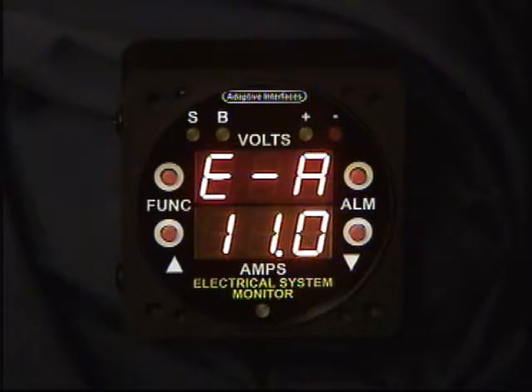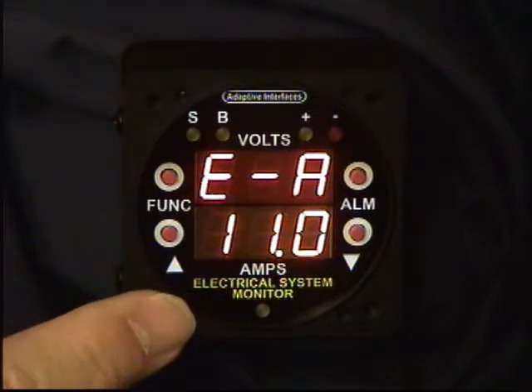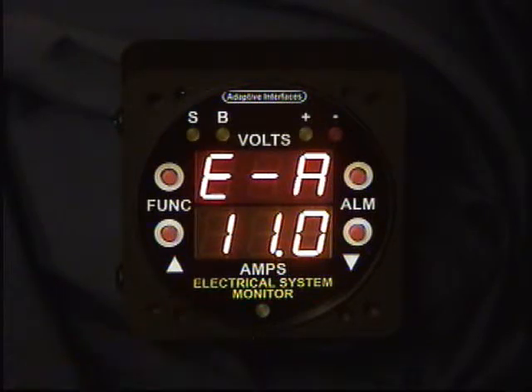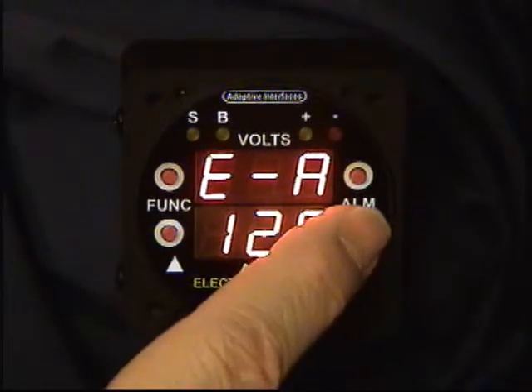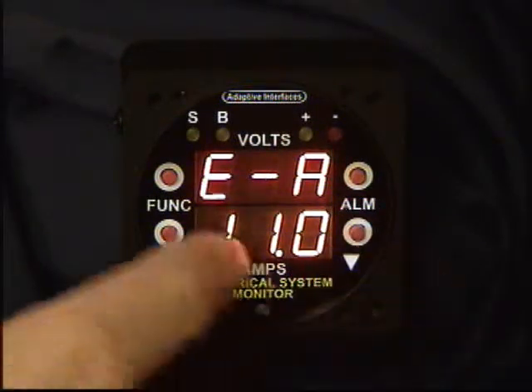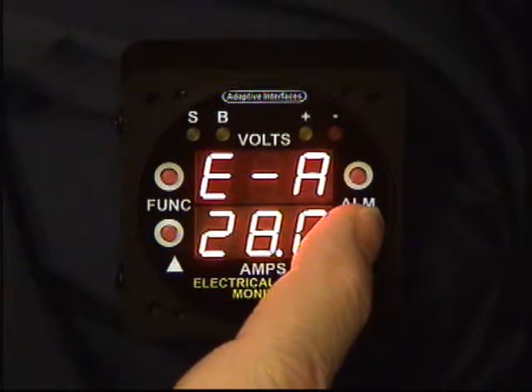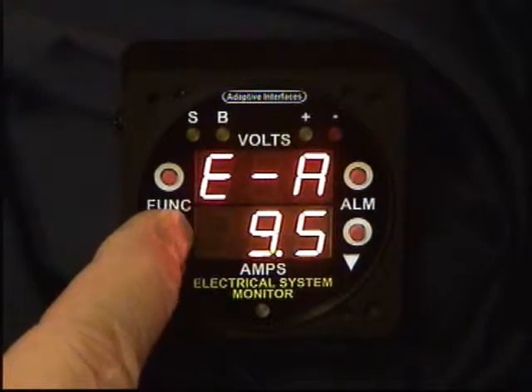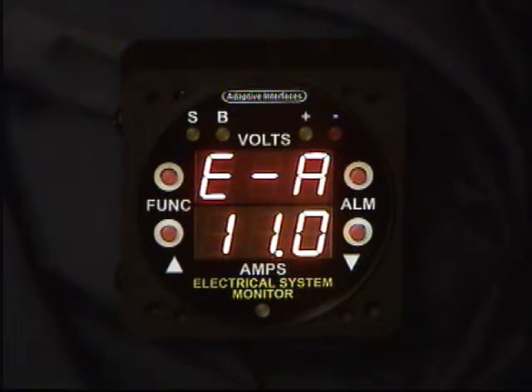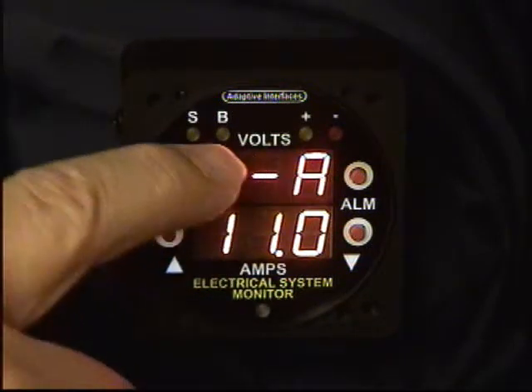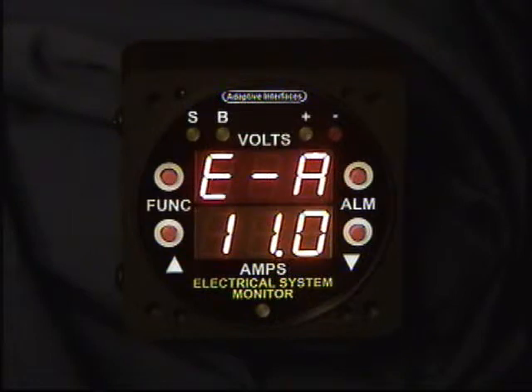Next function, or the next three functions, are alarm levels. Right now, this function here is the voltage alarm level. Right now it's set for 11 volts. It can be changed in half-volt increments all the way up to 28 volts, and down to 9 volts. We'll go ahead and leave it at 11 volts just to show you that it can be changed to different levels. When the alarm is set at 11 volts, a battery or system voltage that drops below 11 volts will cause the instrument to go into an alarm condition, which we'll demonstrate later. If the voltage drops below that, it will flash the voltage display and also output a value out the back of the instrument to drive either a buzzer or a warning light or something like that.